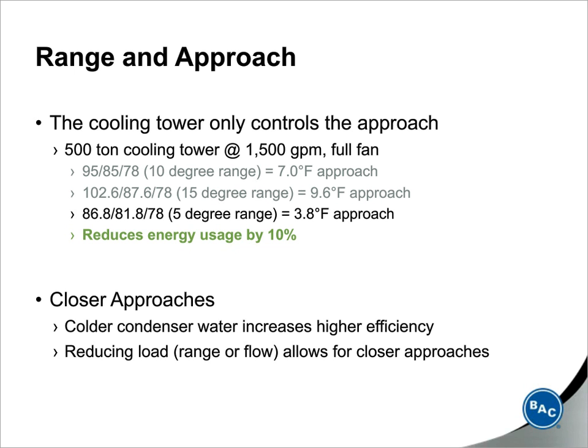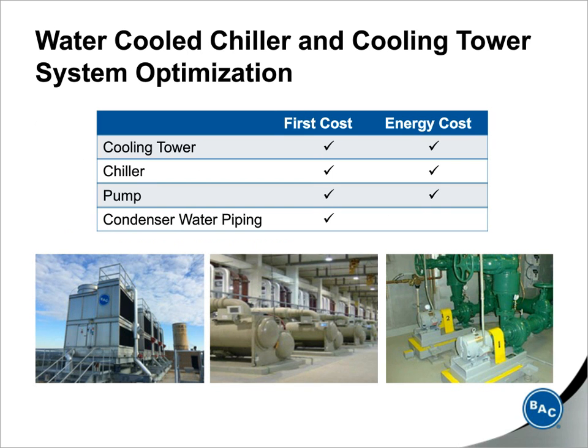So what does that mean? It means that you can either select a smaller chiller or you can run a larger chiller using less energy. So by selecting a higher capacity cooling tower, you really have a great opportunity to reduce this chiller work and cut down on total lifetime costs. Now, when you're optimizing the system to reduce total cost of ownership, always make sure you consider the first cost of the equipment. So that includes the cooling tower, the chiller, the condenser pump and piping, along with associated energy costs.